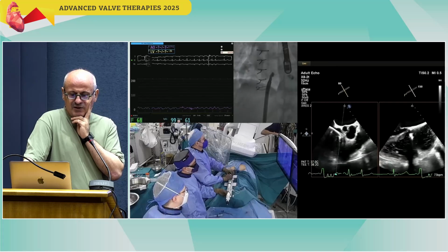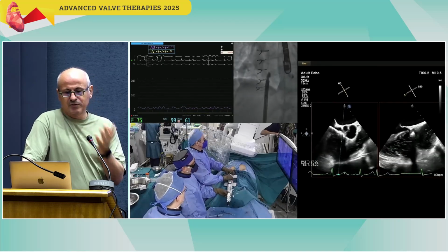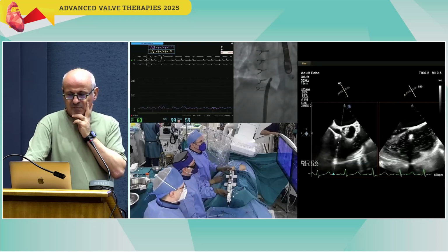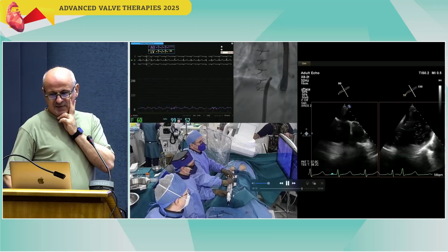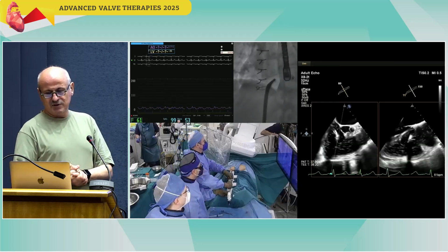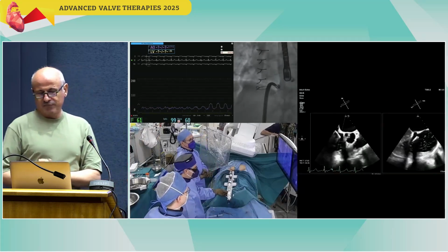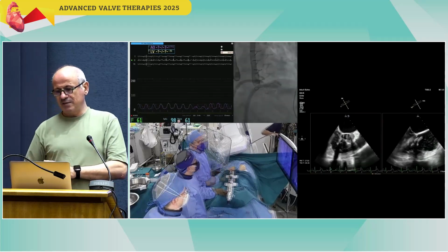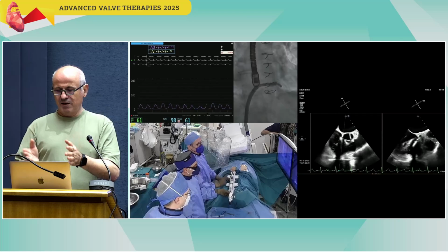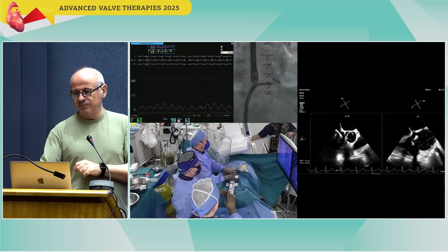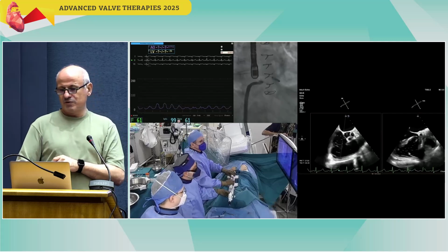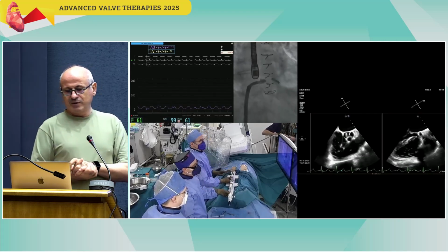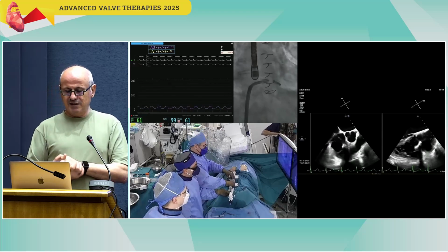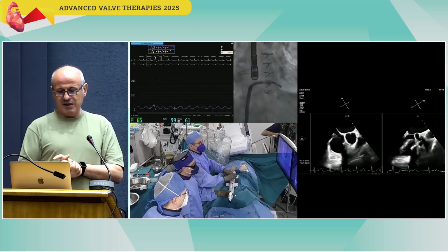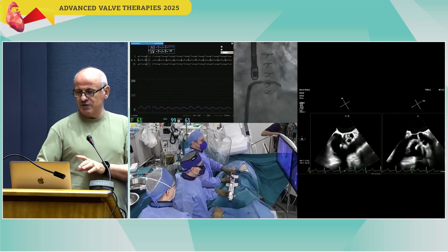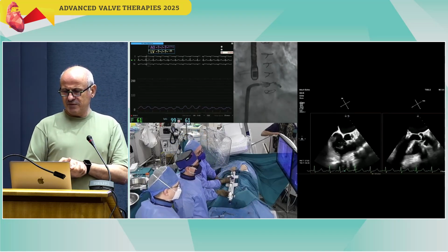So this is coming down. We use the LAO view to avoid the septum, to flex it down to the valve. And then you see the biplane here, midesophageal. We also want to have the trajectories and the positioning of our device in the anterior-posterior and in the septal-lateral. We want to be in the center and the trajectory to be correct. Here you see that our device is very deep. So our device is almost within the valve. To correct this, we should gain height, and we do that by turning the guide catheter counterclockwise and then clockwise on the steerable. And you see how we'll do this, and we'll go higher.